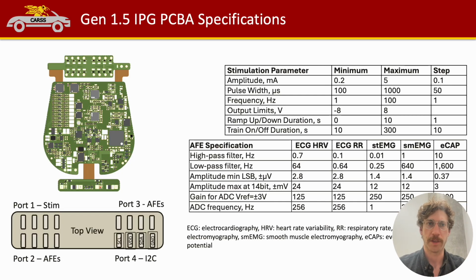Here are the specs for our IPG. This is for the Gen 1.5 PCB. As you can see, there are 8 channels for analog front ends, as well as still the I2C port and stimulation ports. For stimulation output, we're still rating it at 5 milliamps for our maximum output amplitude. For pulse width, we're doing up to 1 millisecond, and then for frequency, we're looking at low frequency stim up to 100 hertz. If you're interested in pushing these boundaries a little bit, please get in contact with us. There are modifications that we could make to extend this if needed.